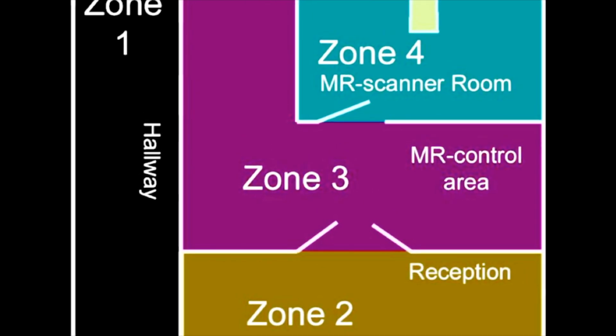Next is Zone 3. Access is restricted by physical barriers such as doors with coded access. Inside Zone 3, only approved MR personnel and patients that have undergone MR screening are allowed. Zone 3 contains the MR control room.